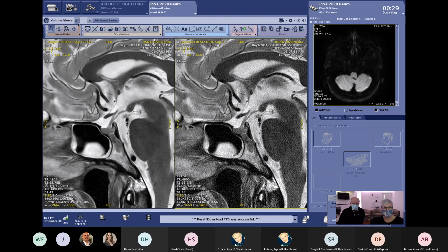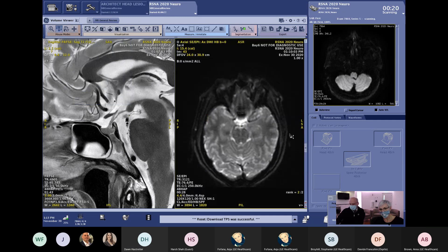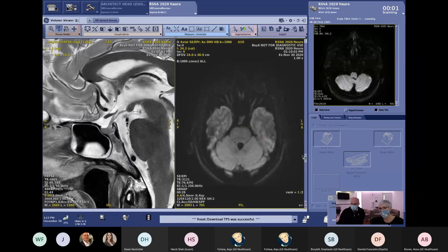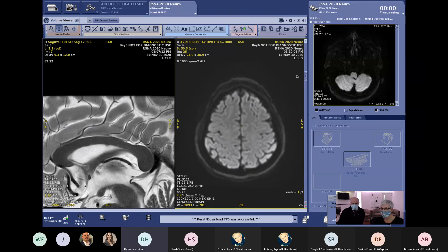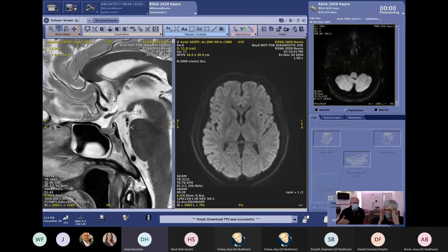We also already acquired the diffusion image done with HyperBand. Going to regions that usually have a lot of distortion — the eyeballs — you can see they are much less distorted than typical. Showing the 1000 b-value, the images are nicely undistorted in a total scan time of 28 seconds. HyperBand is also very useful for diffusion tensor imaging: if you're running 50 diffusion directions, it can significantly reduce the scan time.